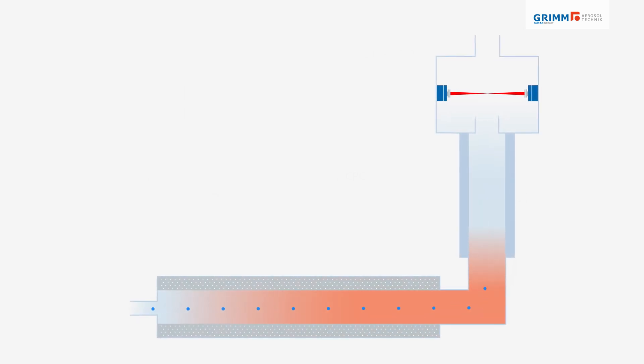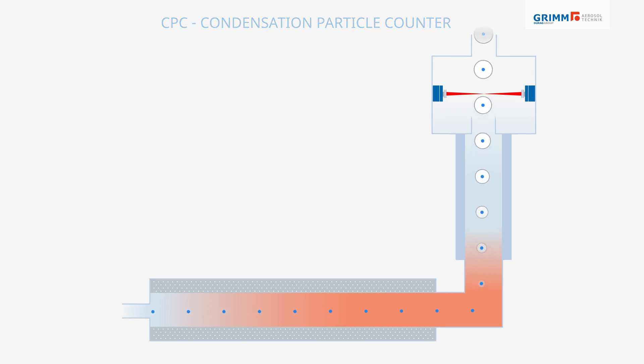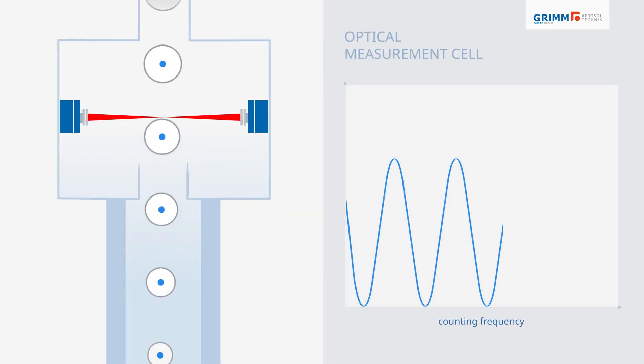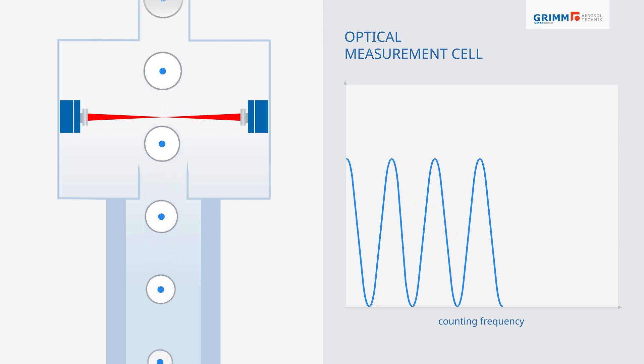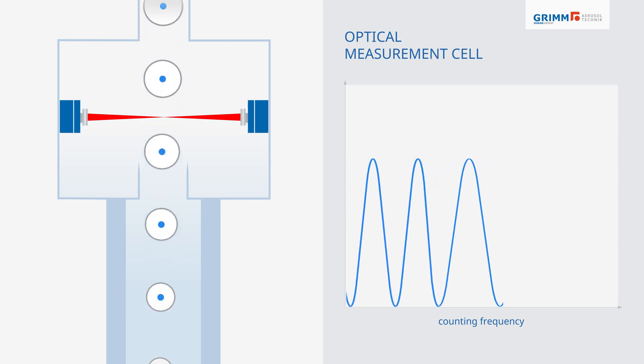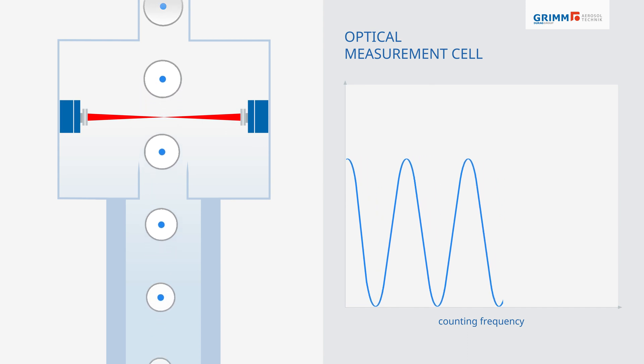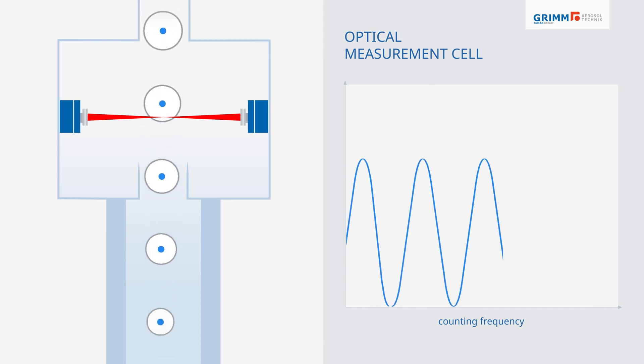Known particle sizes exit the DMA and enter the CPC. A condensation process enlarges all particles to a detectable size. The particles are then counted in the optical measurement cell. With a constant volume flow, the frequency of detected particles results in the number concentration as particles per cubic centimeter.